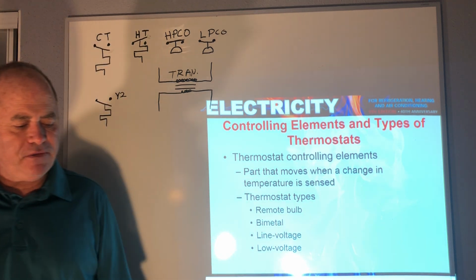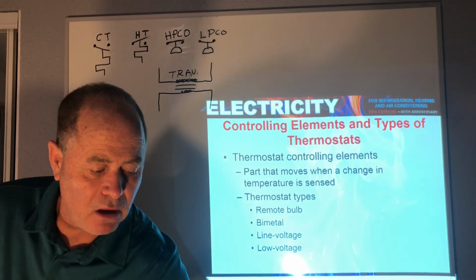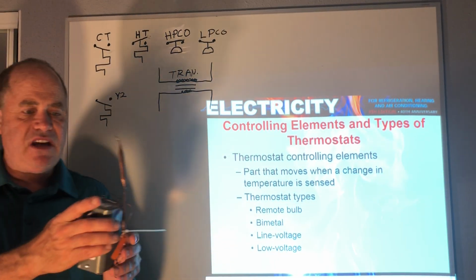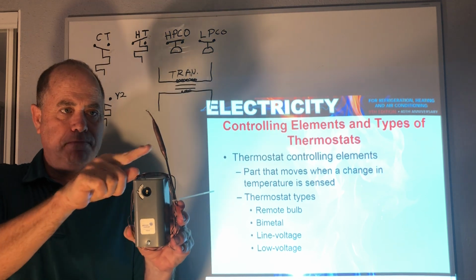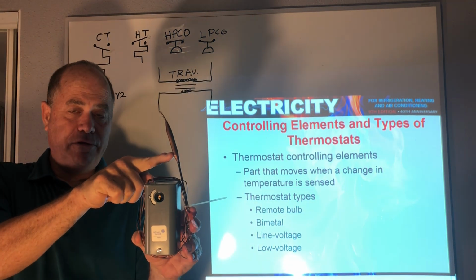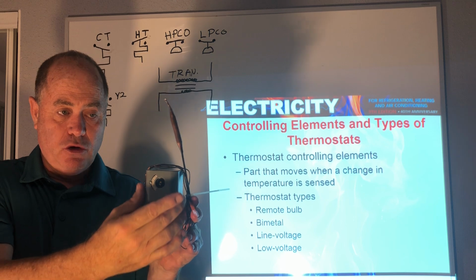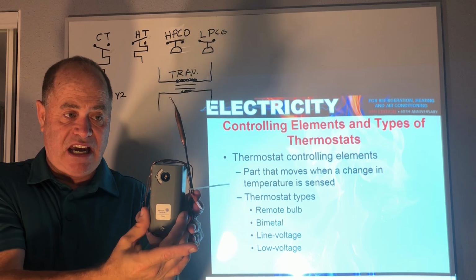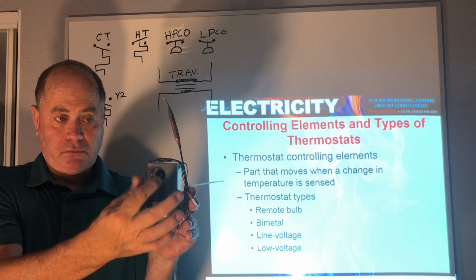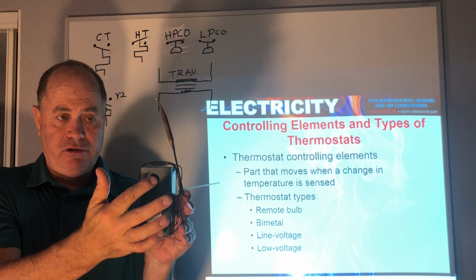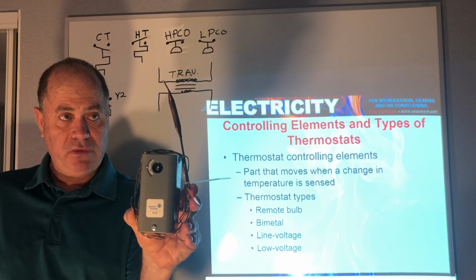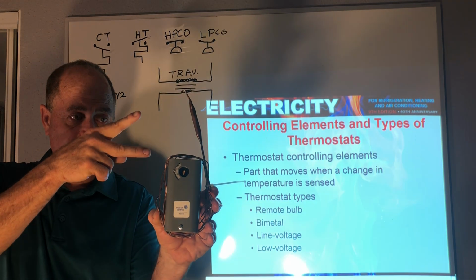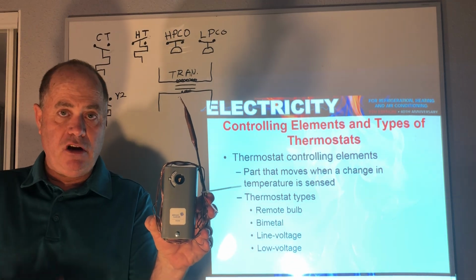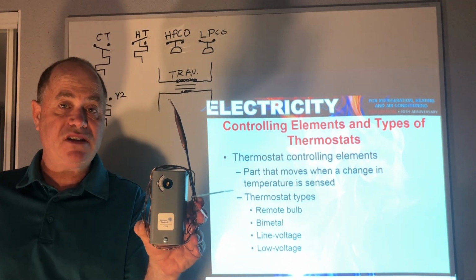We have different types of thermostats. Here we have a remote bulb thermostat, where this bulb can be in the refrigerated space, but the actual control thermostat may not have to be. And you can set the temperature of your refrigerated box here, and then a set of contacts opens and closes to bring on cooling when the box gets too warm.